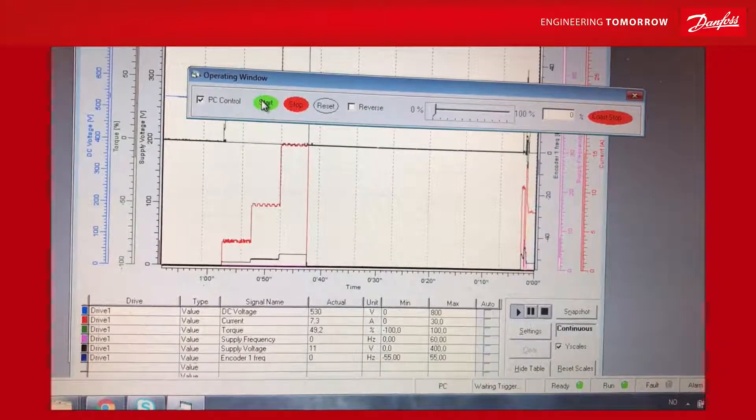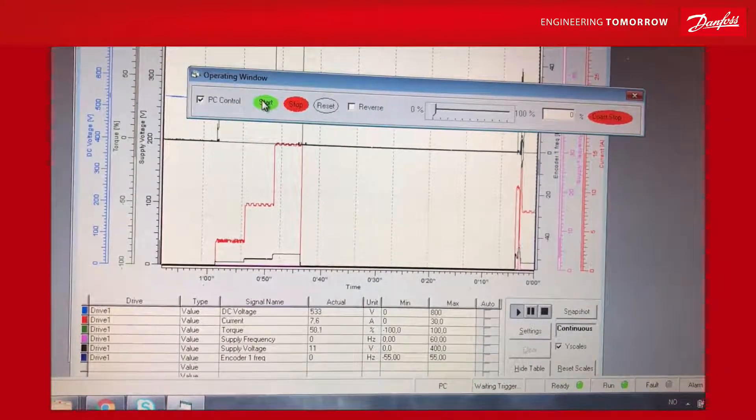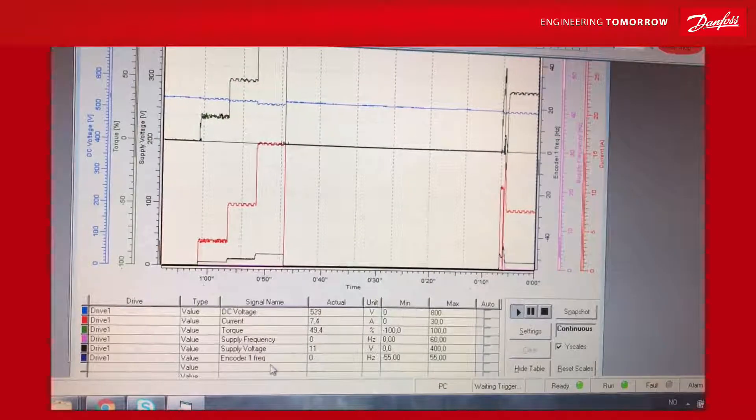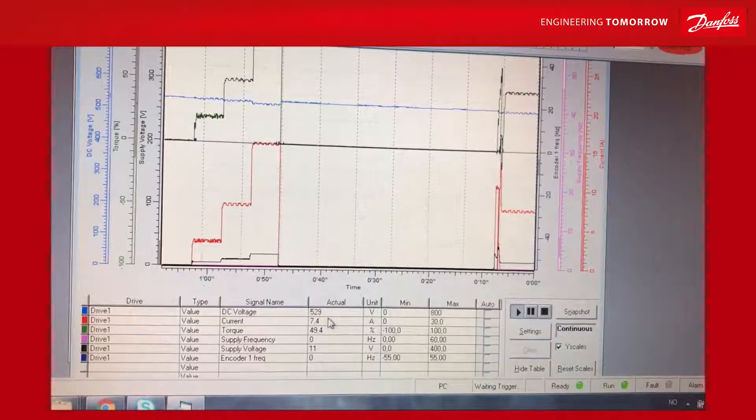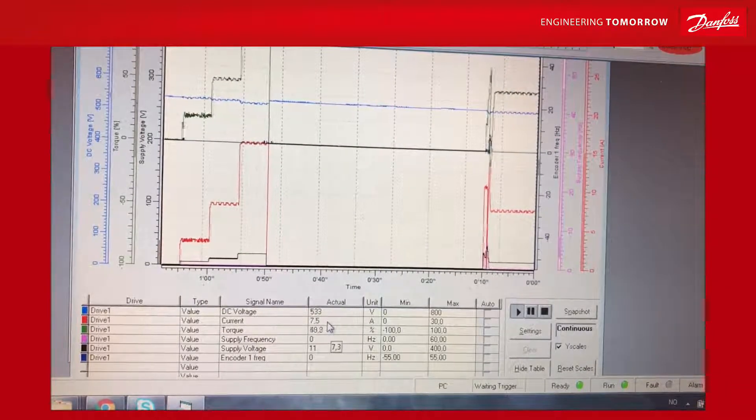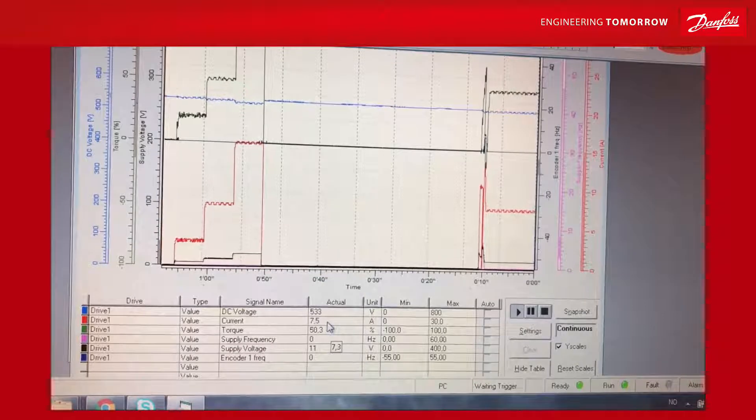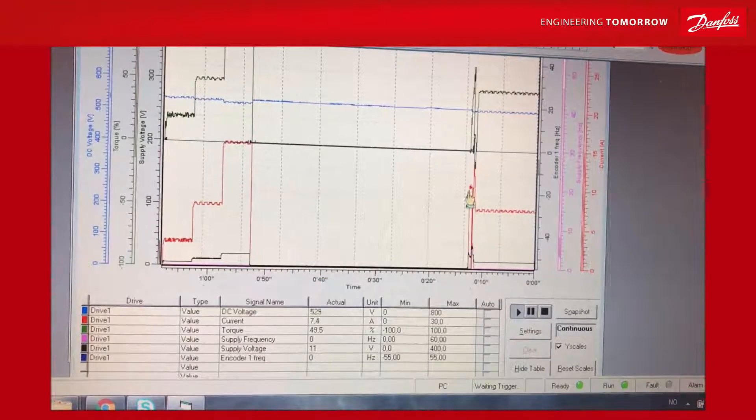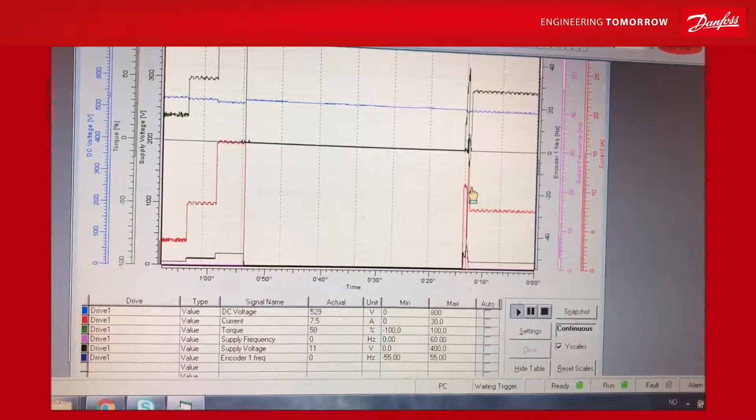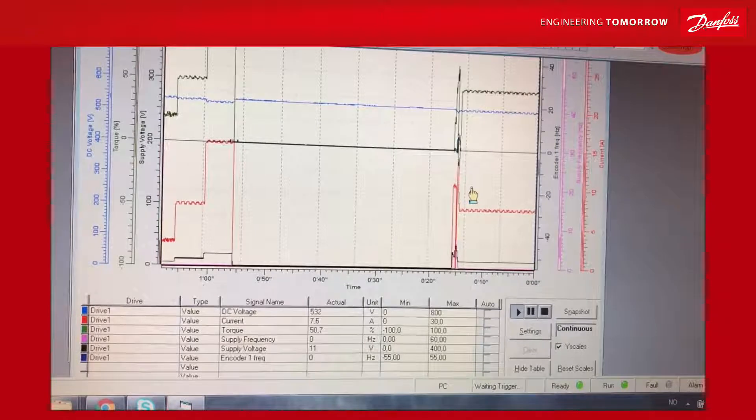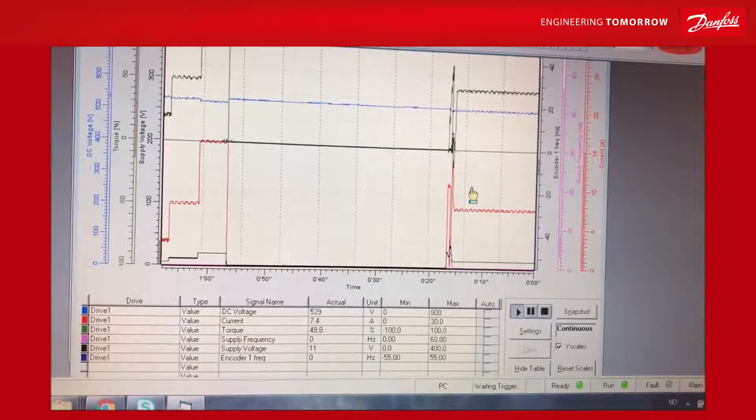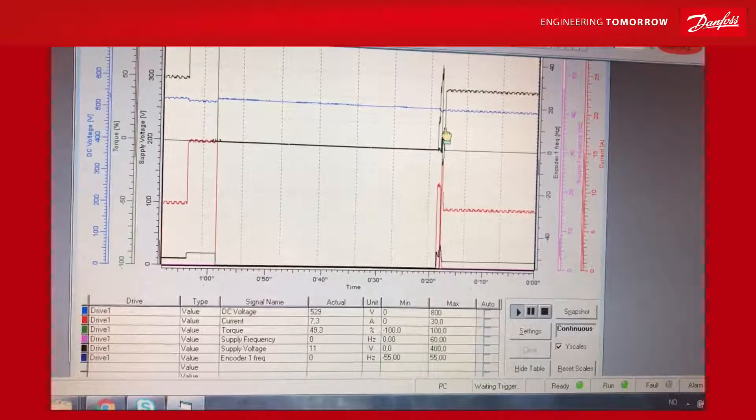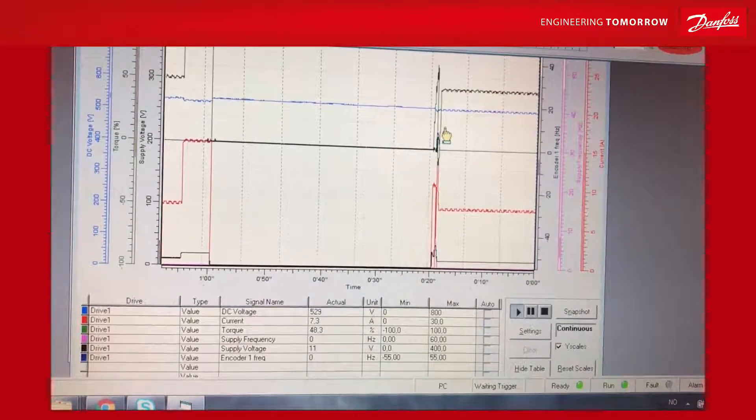It did a jolt, and that was basically when magnetizing the stator. It doesn't know where the rotor poles are, which causes this movement. Be aware that starting up in open loop for the first time, there will be movement on the motor.